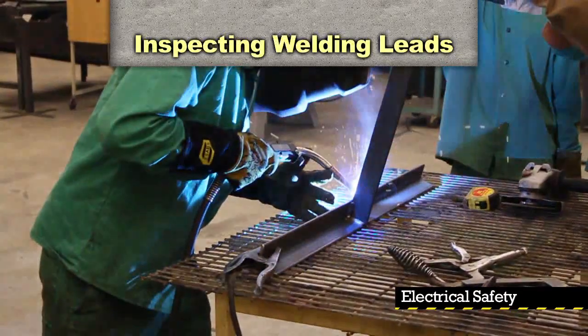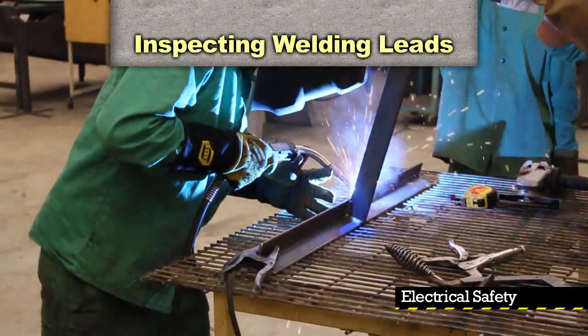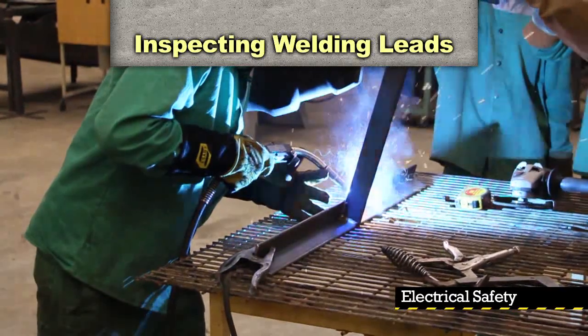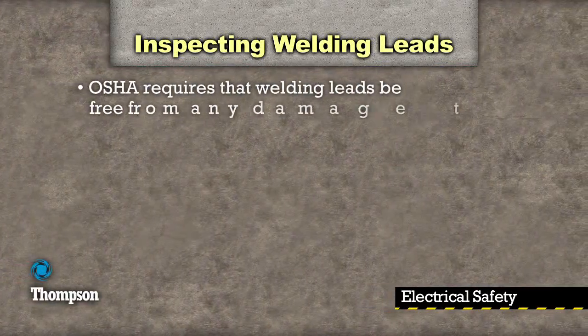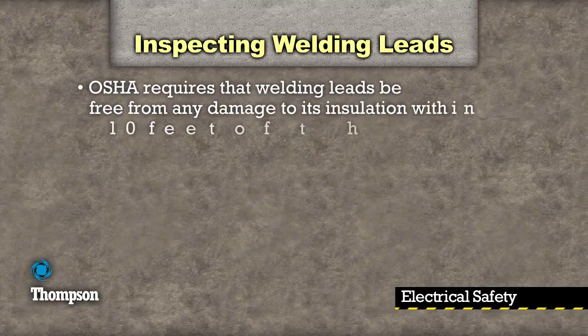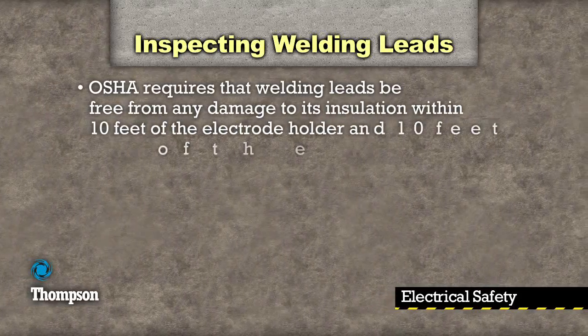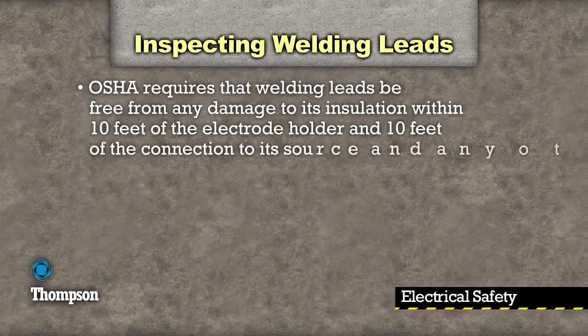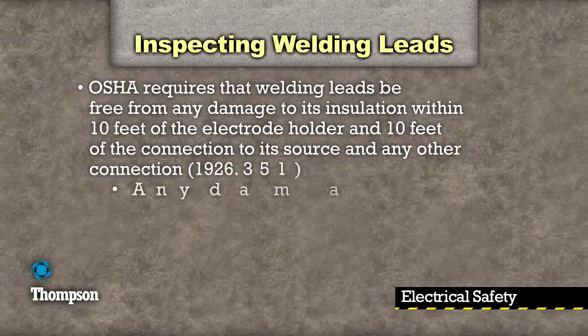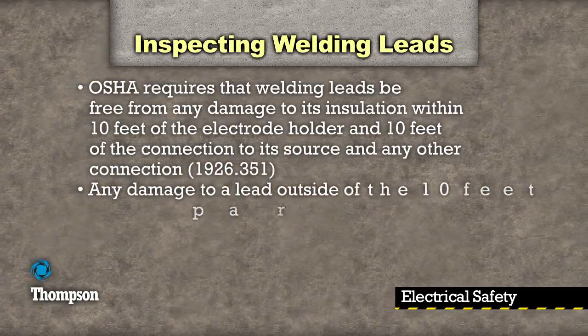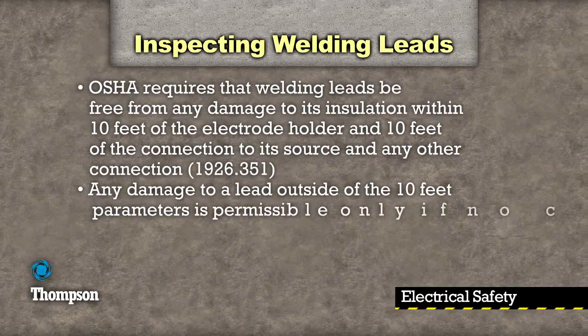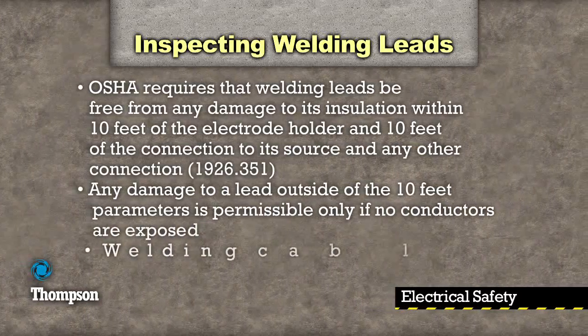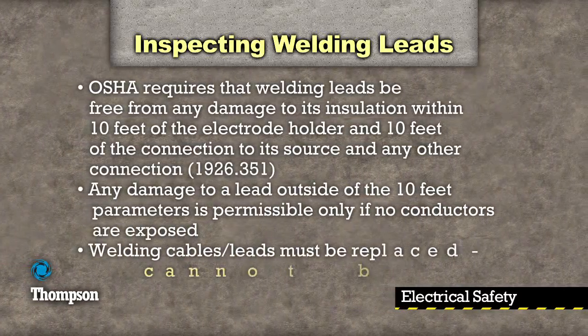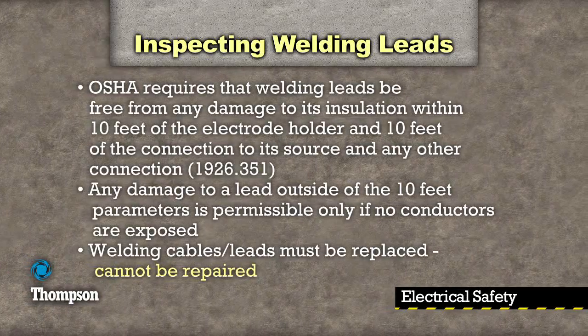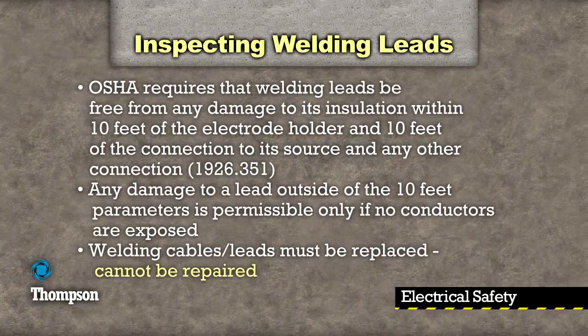We do a lot of welding at Thompson, and like electrical cords, welding leads must be inspected prior to each use and tagged quarterly. According to OSHA, welding leads cannot have any damage to its insulation within 10 feet of the electrode holder and 10 feet of the connection to its source or any other connection. Any damage to the insulation outside of the 10-foot parameters is permissible only if no conductors are exposed. OSHA also requires that damaged welding leads must be taken out of service and replaced.